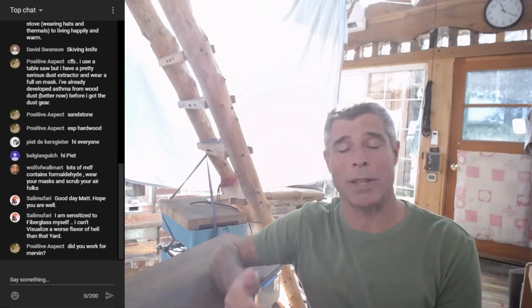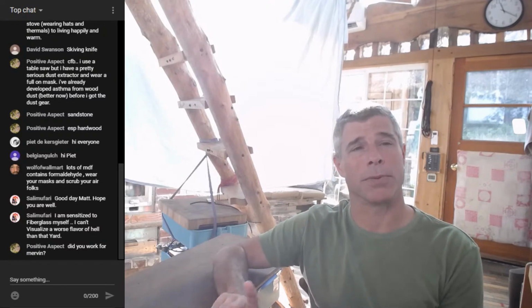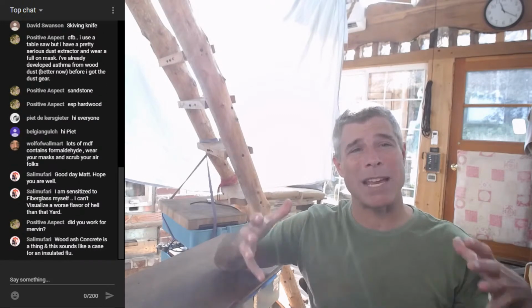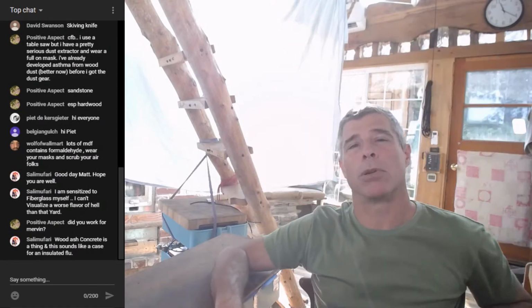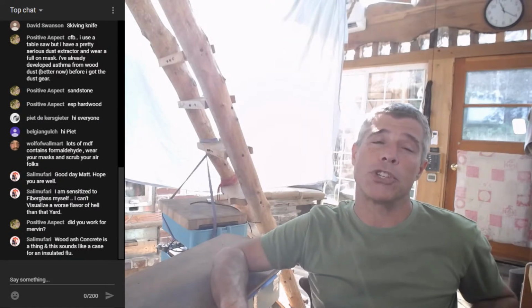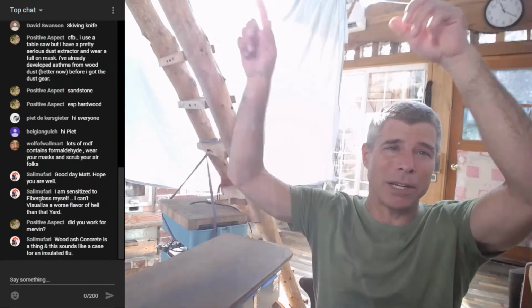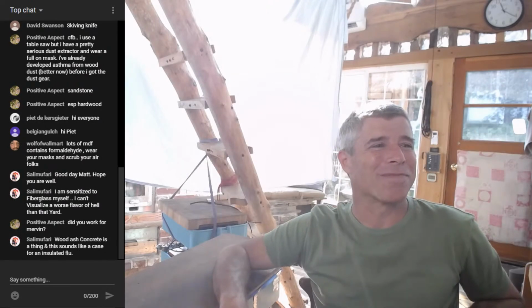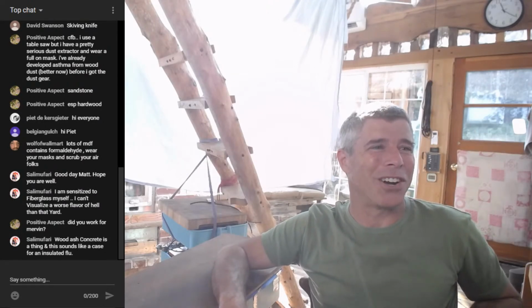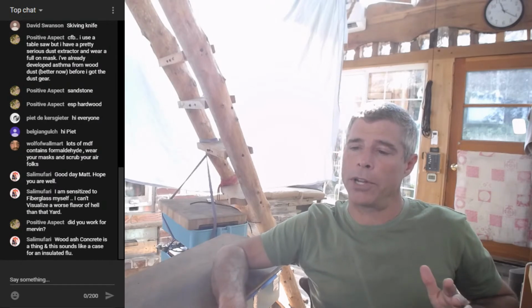So this is one of the main reasons why insulated flue pipes are so useful and such a great recommendation. More than anything, it's because they maintain stack temp all the way to the top, and they give you a much better chance of blowing your moisture out of the chimney rather than just having it recondense and getting a stack rain cloud in there. So really, really important component.